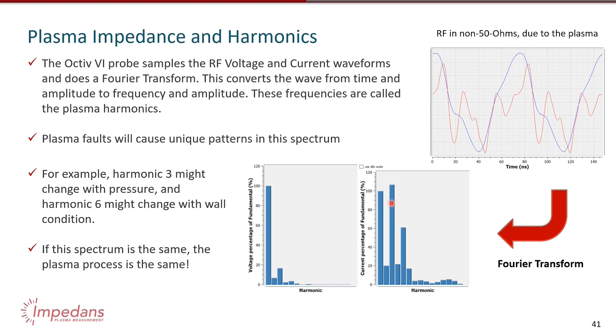Changes in that circuit will change the impedance that you measure, but these harmonics are really sensitive to changes in that impedance, and they are specific to the different things that change that I mentioned on the previous slide. So by monitoring these harmonic levels, you can get really high sensitivity to plasma chamber changes. And that's usually what we recommend for process repeatability monitoring and so on.